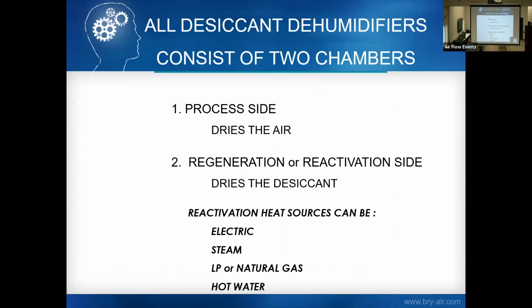We have two different sides of our units: the process side and what we call the reactivation side. The process side is what dries the air. Whether it's outside air, return air, or a mix of outside and return air, it goes into our unit and then enters the desiccant rotor. As it enters the desiccant rotor, the moisture is absorbed. The desiccant rotor rotates at a very slow speed, around 3 RPH to about 15 revolutions per hour. As it rotates, the desiccant rotor enters our reactivation air, which basically releases the moisture back into the exhaust of the unit.